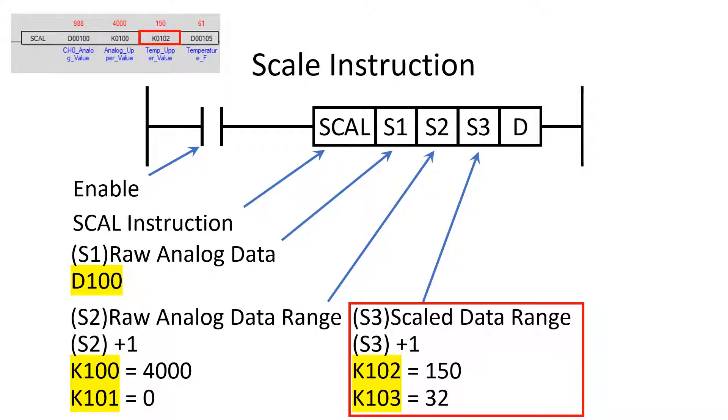The S3 operand stores the scaled range of the analog device. In this program, the scaled range is 32 to 150 degrees with a 1 degree resolution. S3 uses two memory locations just as S2. In this program, it is K102 and K103 as shown.